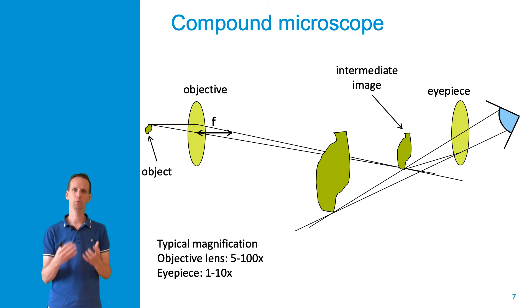In a compound microscope we first have an objective lens that makes an image of an object. You can see that image in the diagram here depicted as the intermediate image. The intermediate image is then focused upon by the eyepiece, which forms an image to the observer, just like we would have for a single-lens system where an observer looks through the lens.